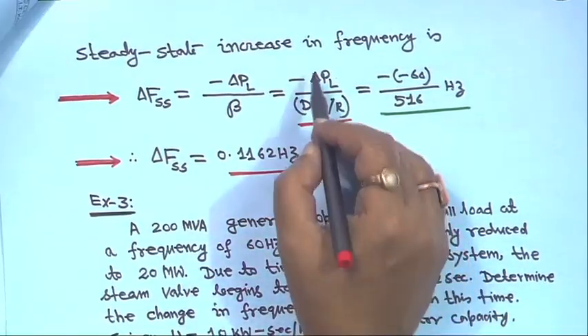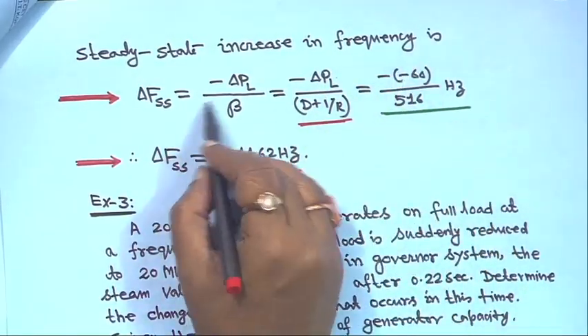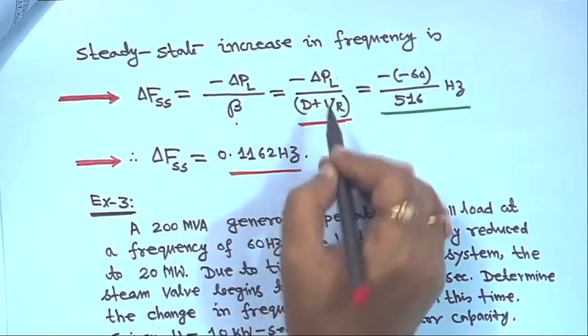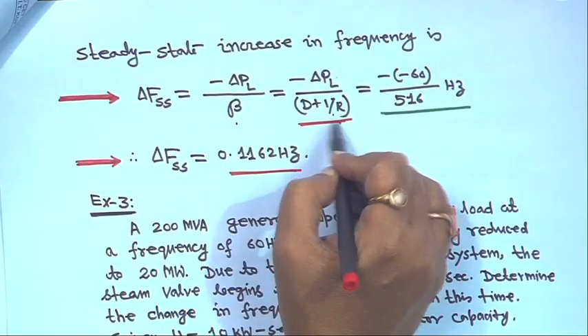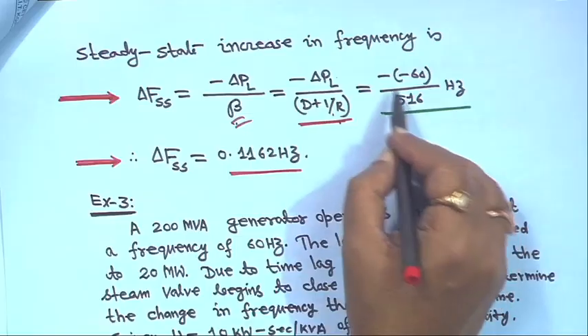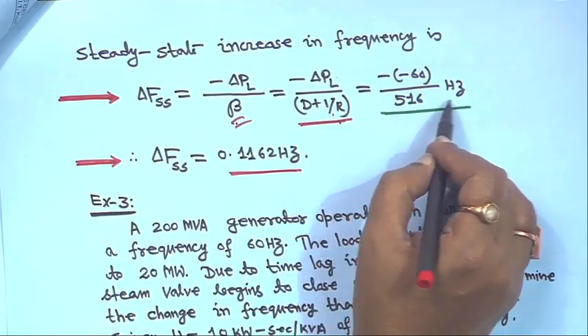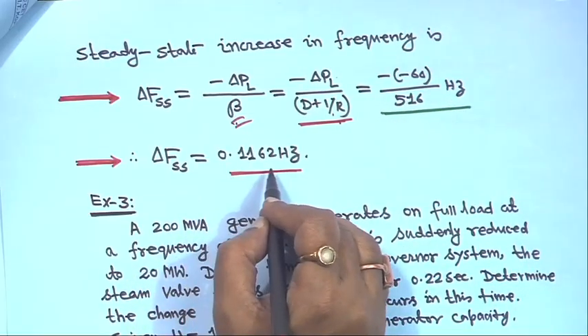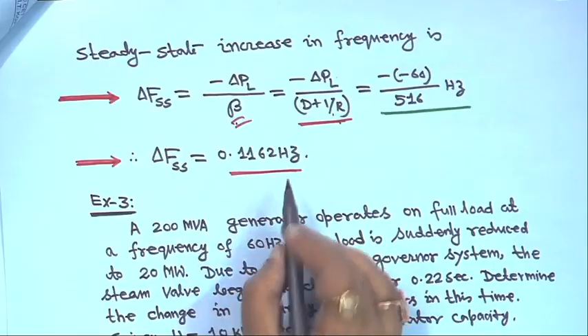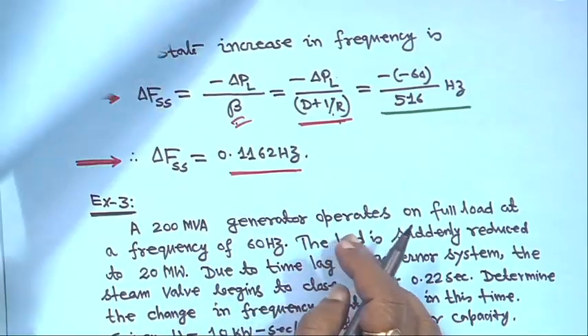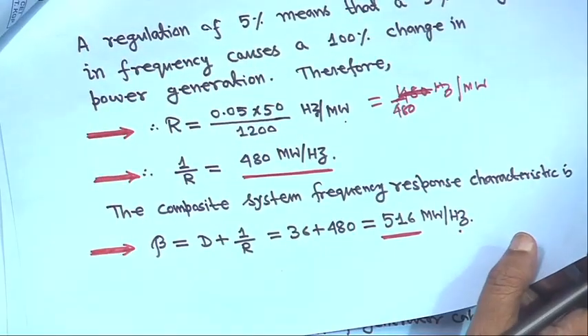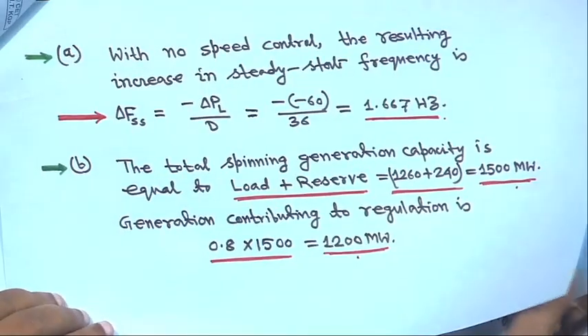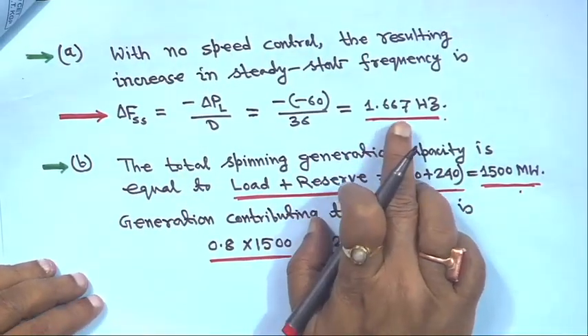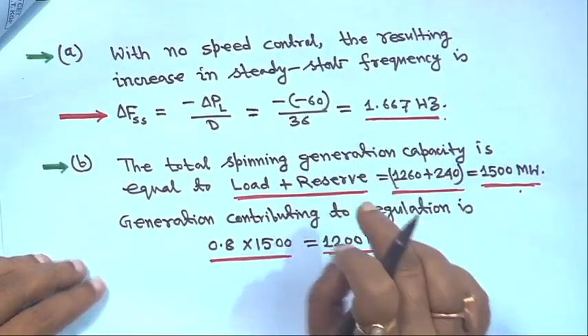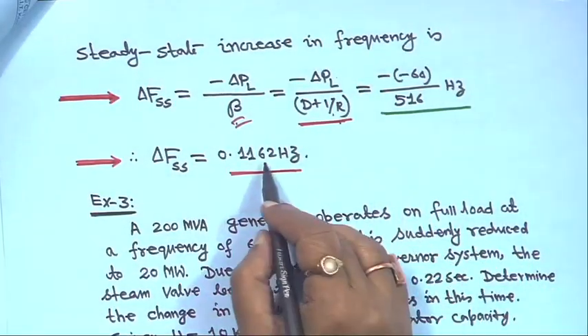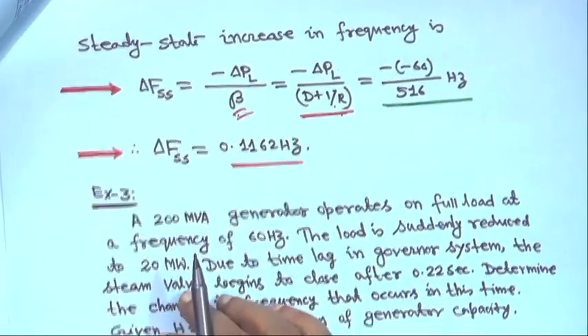Now the steady state increase in frequency is delta FSS equal to minus delta PL upon beta, that is minus delta PL upon D plus 1 upon R. Beta we have calculated as 516. So minus of minus 60 by 516 hertz, and delta FSS will be 0.1162 hertz. So what we have seen: with no speed control it was 1.667 hertz, and when we consider everything, it is 0.1162 hertz.